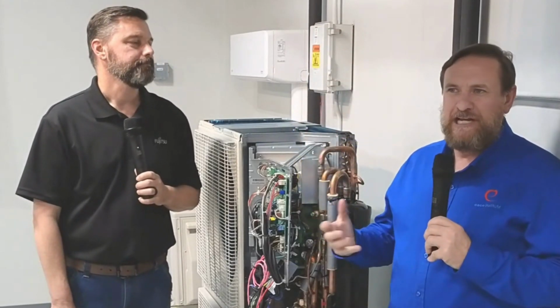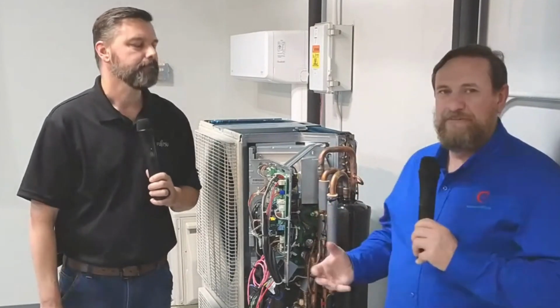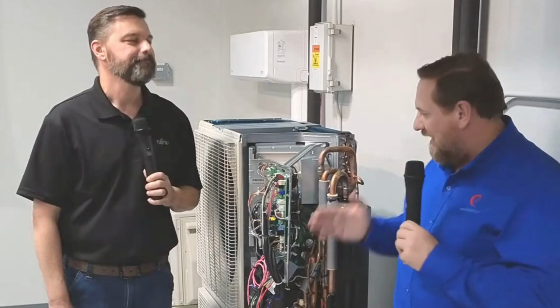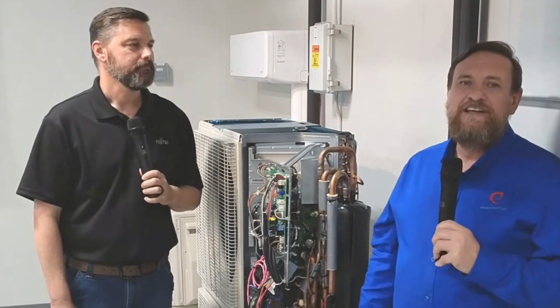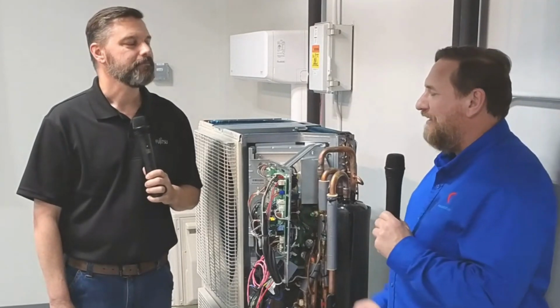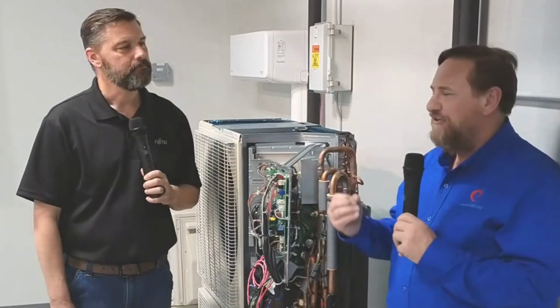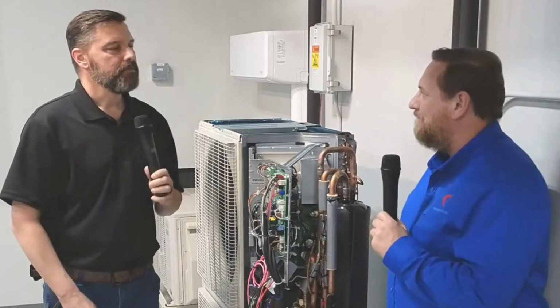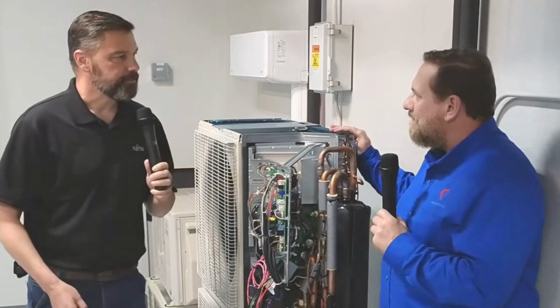And we always hear people talk about, well, what if moisture freezes in the system? If you wait for an hour on that system, if there's any moisture in there, the heat exchange of all of this tubing is going to have that ice melting very quickly back into a vapor. You're going to see it very quickly on that micron gauge. So I love the fact that it's so specific and uses that long enough to hit the decay time. So that's part of that learning process.